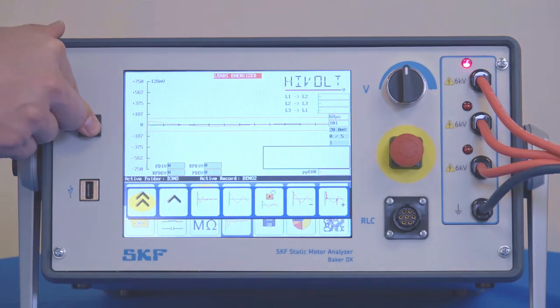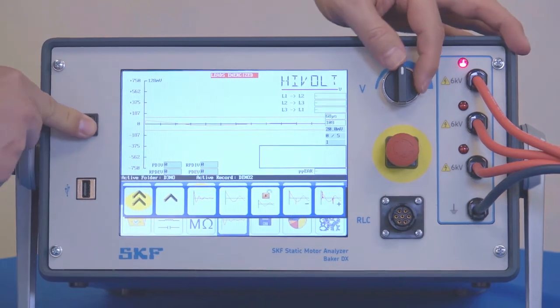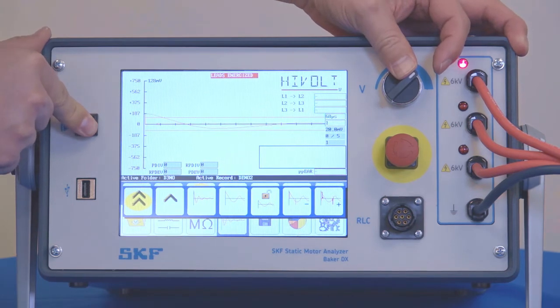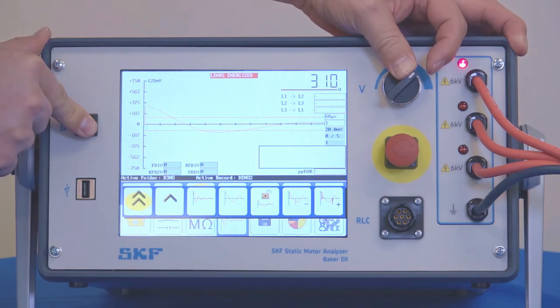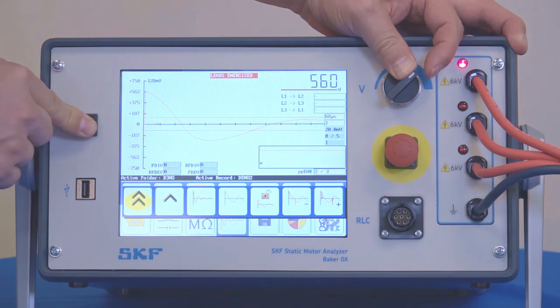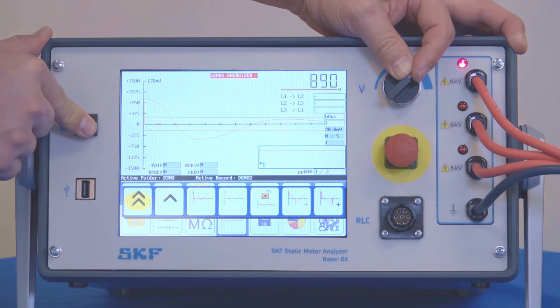Our scales are set and we're ready to ramp. Go ahead and increase the test voltage again just like we did for the normal surge test. What we're looking for now, a little bit different, is the partial discharge inception voltage and repetitive partial discharge inception voltage to populate.